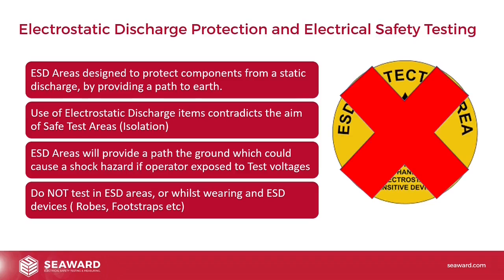If you do work in an area that has ESD protection, you will need to create an isolated test area separate from that ESD protection where testing will take place. And by all means follow the ESD procedures up until the edge of that test area to keep the equipment safe. But once that equipment is being tested and in the test area, our main concern is keeping the operators safe.